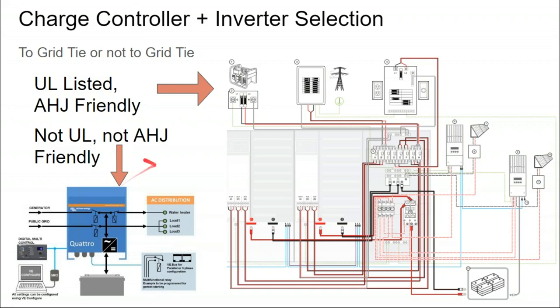So I've tried it both ways. I've tried high-end battery inverters that have multiple purposes and functions, that can be grid tied, that can be stackable, and in some cases - not every manufacturer supports this - you can combine battery inverters with other battery inverters of different manufacturers and have them in different modes of operation to do different energy management things. For example, you could have a flooded lead acid battery on base load, and a separate lithium ion battery inverter handling peak loads. That would elevate both parts of the system.